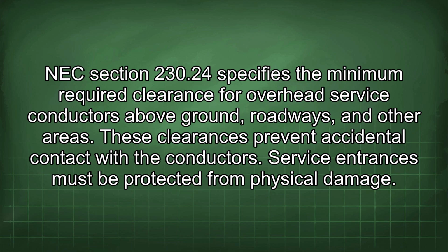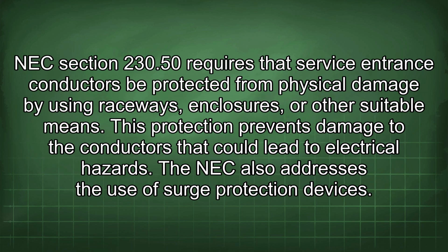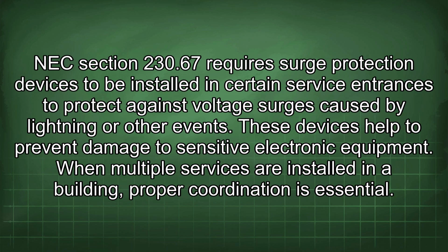Service entrances must be protected from physical damage. NEC Section 230.50 requires that service entrance conductors be protected from physical damage by using raceways, enclosures, or other suitable means. This protection prevents damage to the conductors that could lead to electrical hazards. The NEC also addresses the use of surge protection devices. NEC Section 230.67 requires surge protection devices to be installed in certain service entrances to protect against voltage surges caused by lightning or other events. These devices help to prevent damage to sensitive electronic equipment.